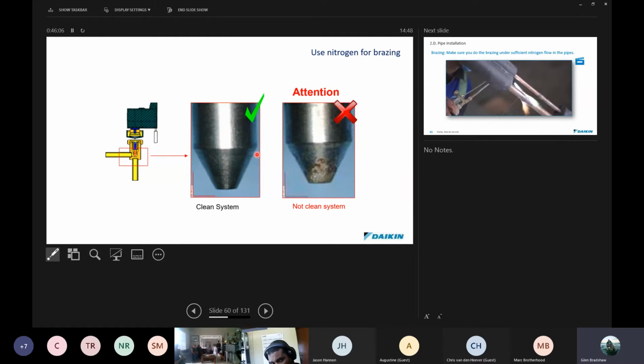In a system that is contaminated, what often happens is it damages the needle part of the expansion valve, and this doesn't seat properly in the needle and seat operation. Expansion valves in today's environment, electronic expansion valves, seal off 100% in a system. So in a case like this, we'd have constant refrigerant bleeding through, and this could have a detrimental effect, both in noise or, if it's significant enough, the unit might carry on cooling, or even heating. So we want this tip over here on the expansion valve to be protected. We don't want any dirt in the system. In a non-clean system, this is the type of thing that we're going to see. Acid buildup over time in a system, if not dealt with, can also cause these surfaces to become damaged. So when welding a system, it's important that we use the correct amount of filler rod and the correct amount of heat.